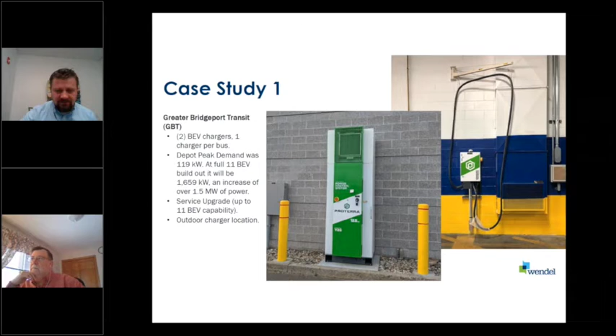So that gave us a target to shoot for, and after analyzing the existing electrical demand at the depot, which was actually 119 kilowatts, it was determined that an electrical service upgrade was needed to accommodate the additional 1.5 megawatts worth of power. So our team has designed the new electrical service, which included main switchgear replacement as well as the service transformer.